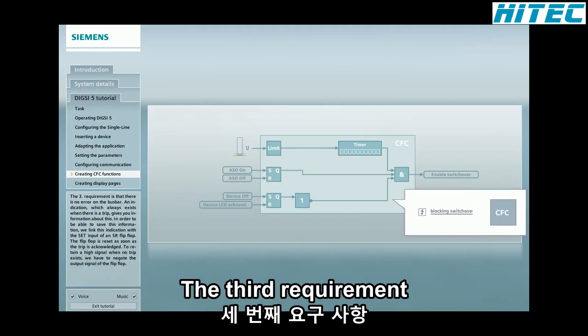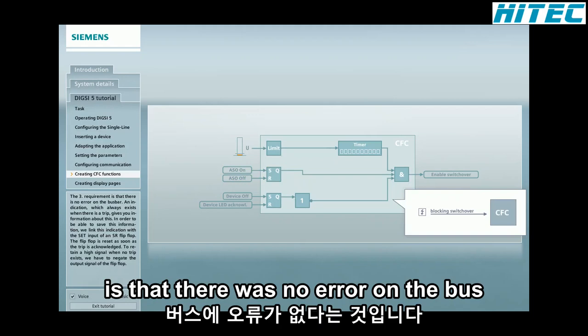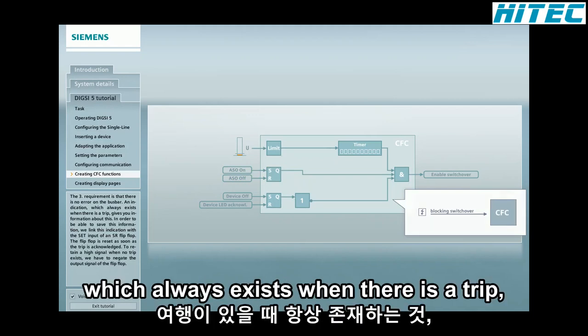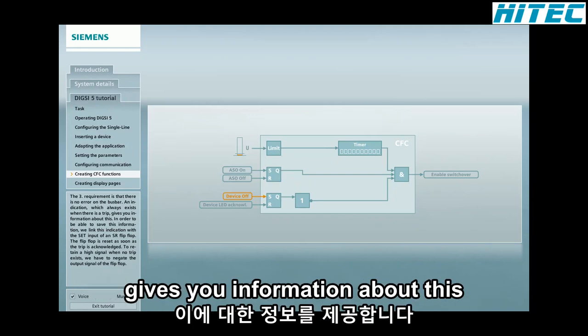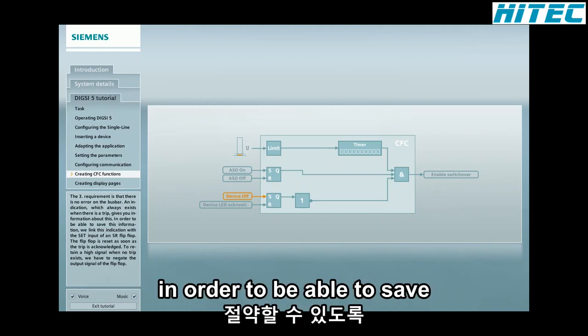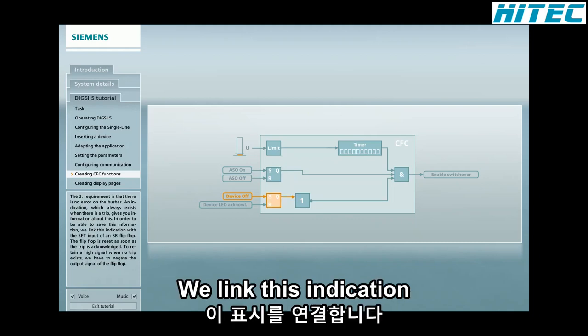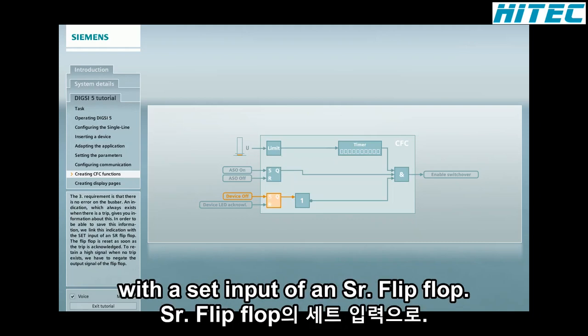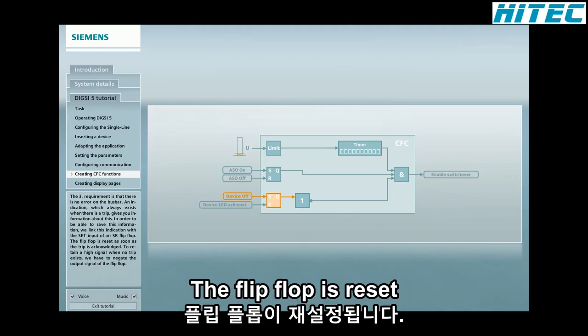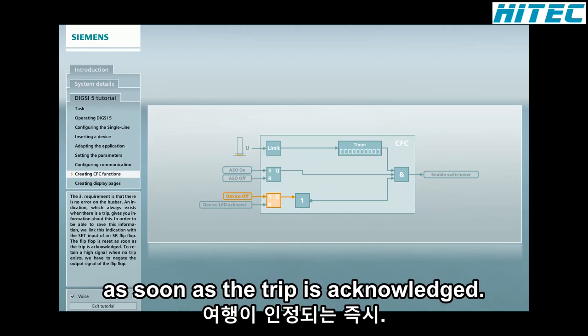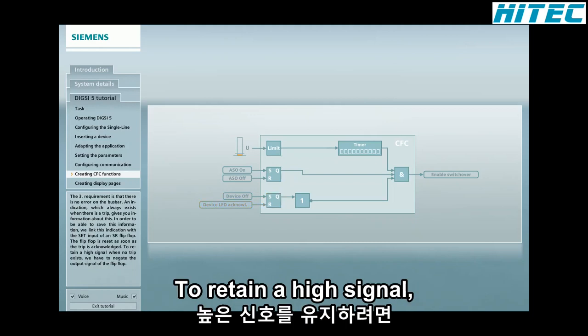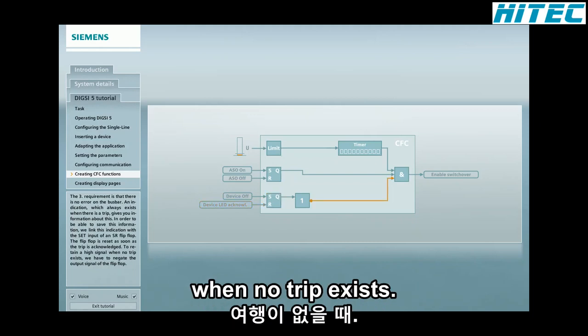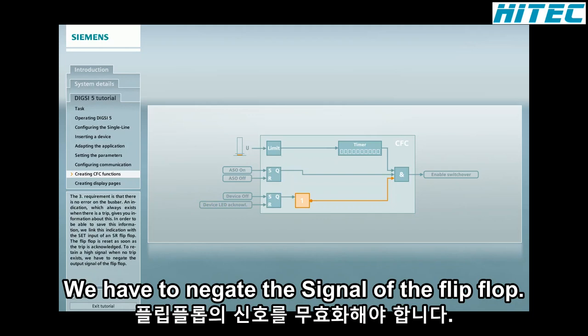The third requirement is that there is no error on the busbar. An indication which always exists when there is a trip gives you information about this. In order to be able to save this information, we link this indication with a set input of an SR flip-flop. The flip-flop is reset as soon as the trip is acknowledged. To retain a high signal when no trip exists, we have to negate the output signal of the flip-flop.